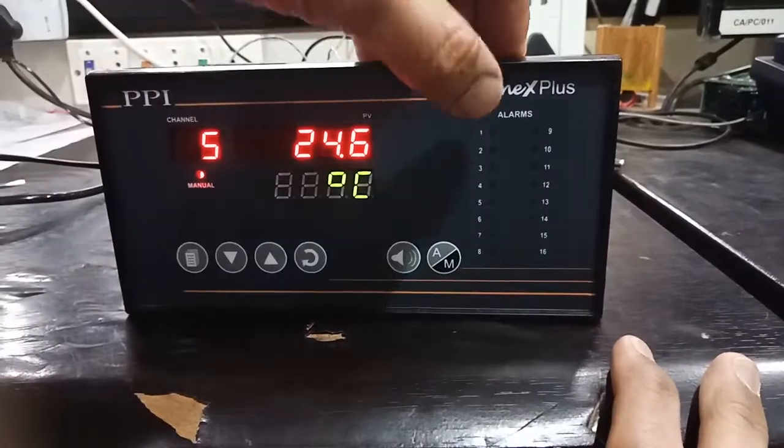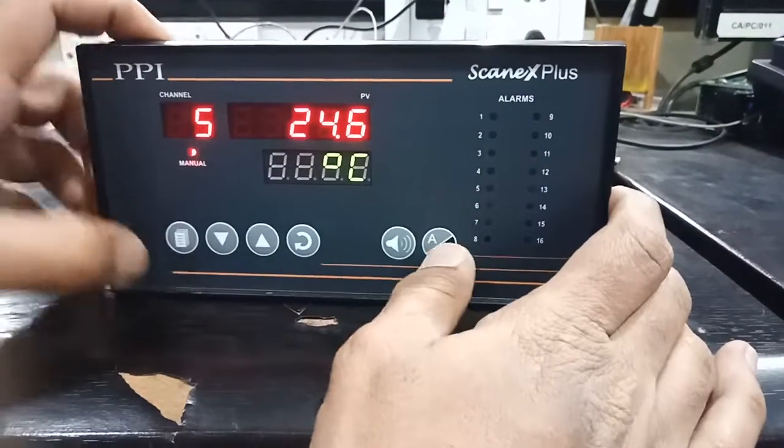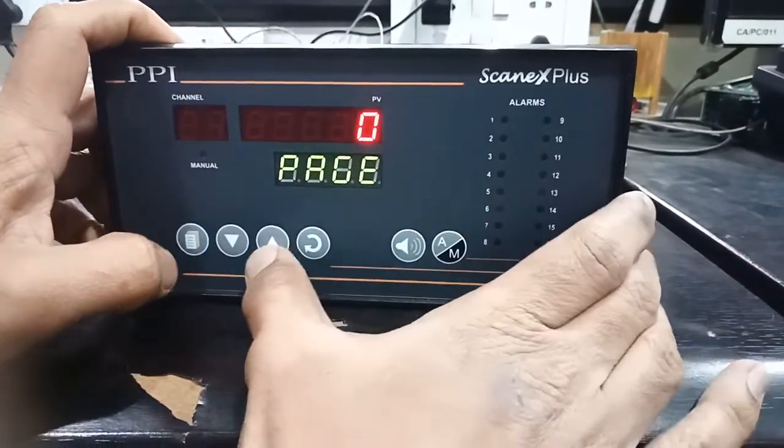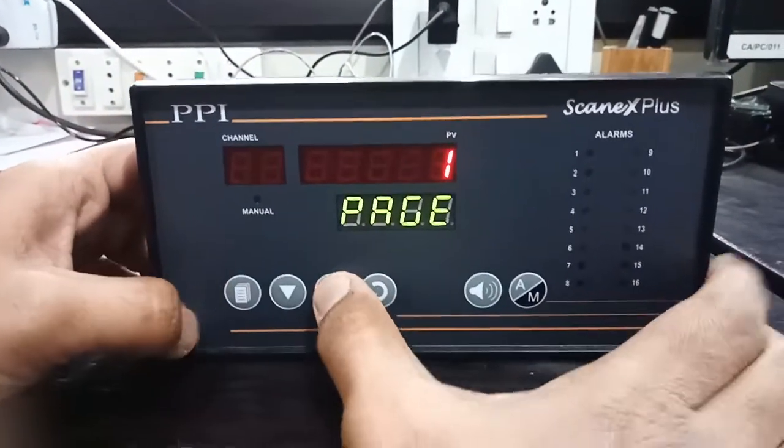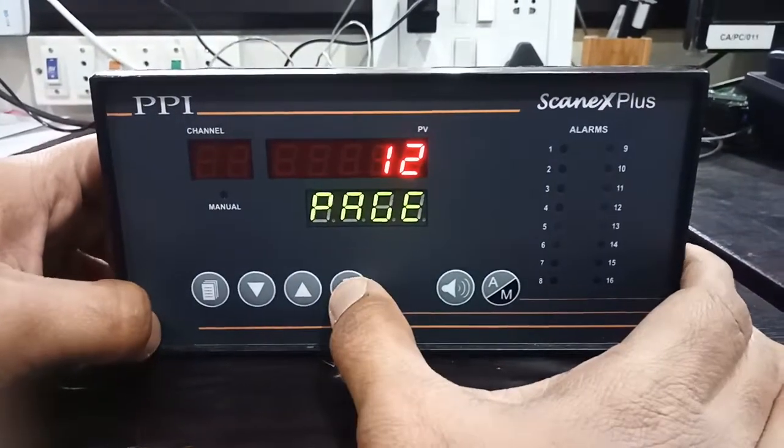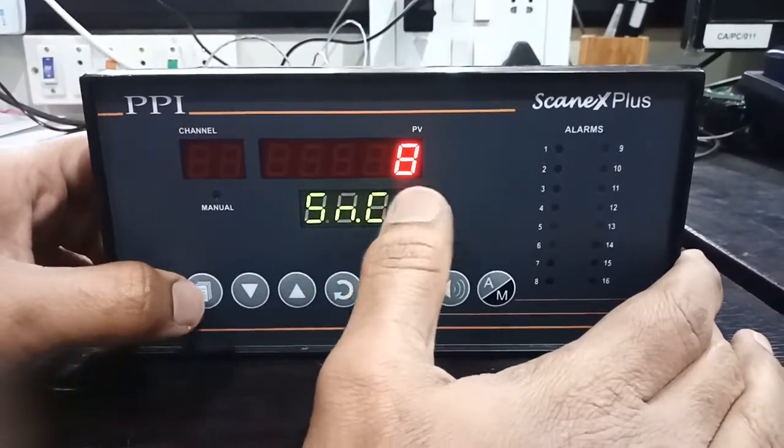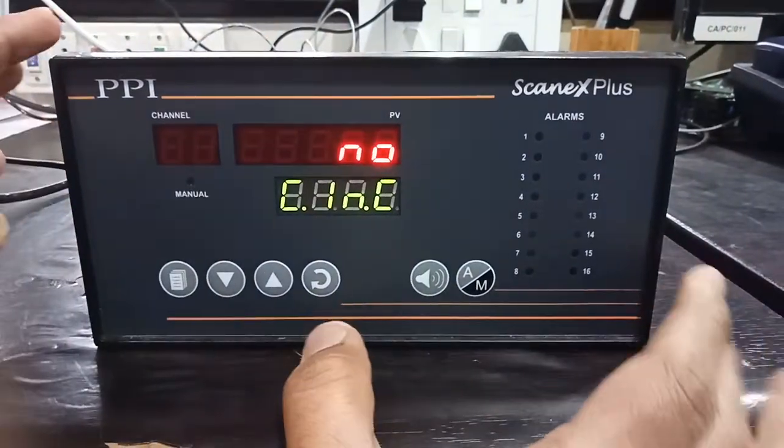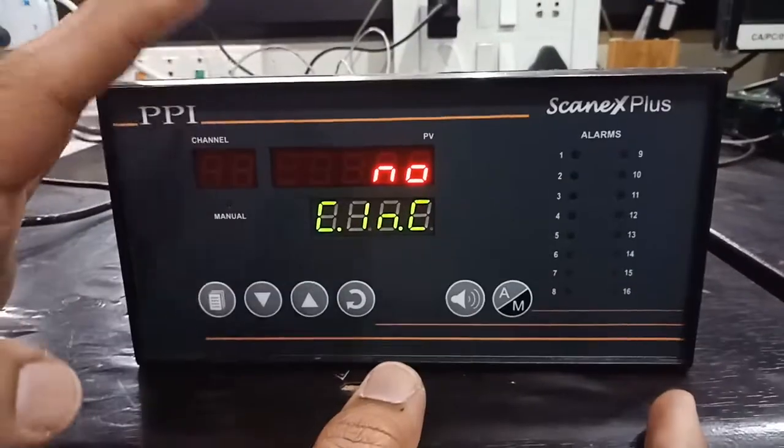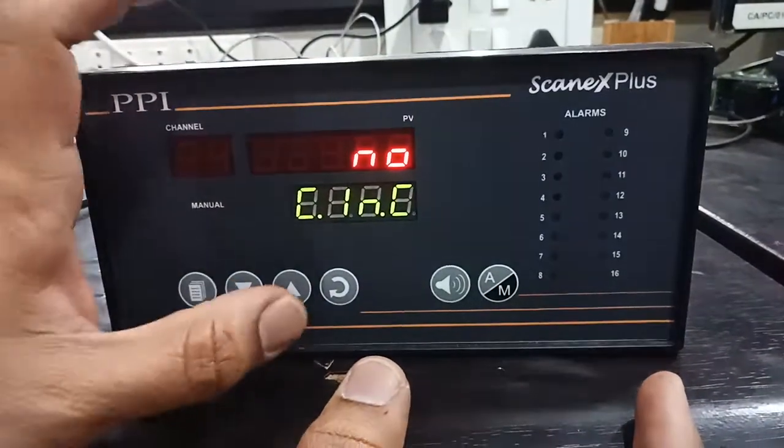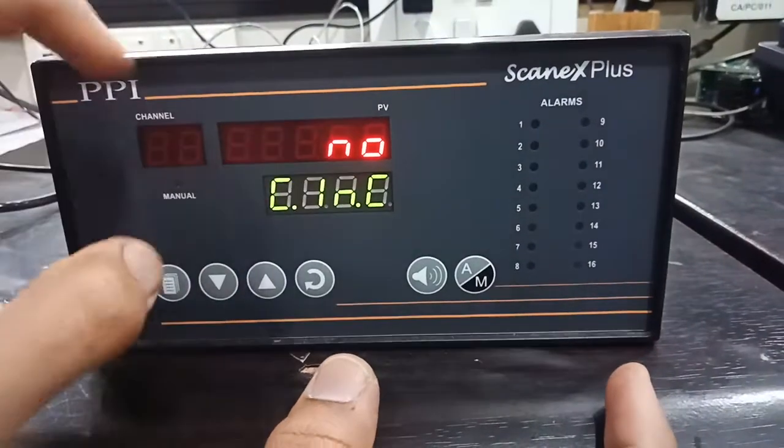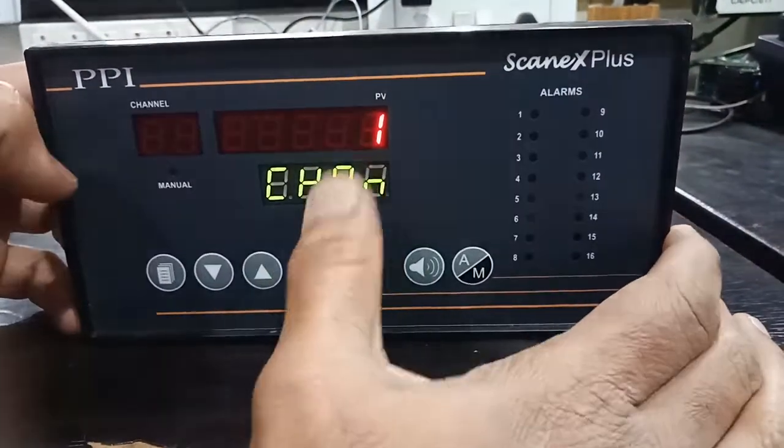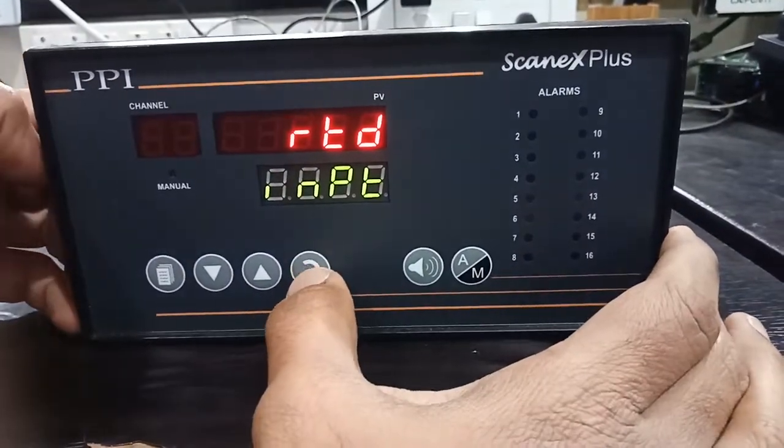For setting the input configuration, you have to press the page button and go to page number 12 to set the input values. Then scan channels: number of channels to scan is 8. Press enter key. If you are selecting all channels with the same input, select CINC value as yes, which means common input channel terminals. Since you are selecting different channel types or input types, make it as no and press enter. Select channel 1, select the input type as RTD or thermocouple, whichever input you selected.